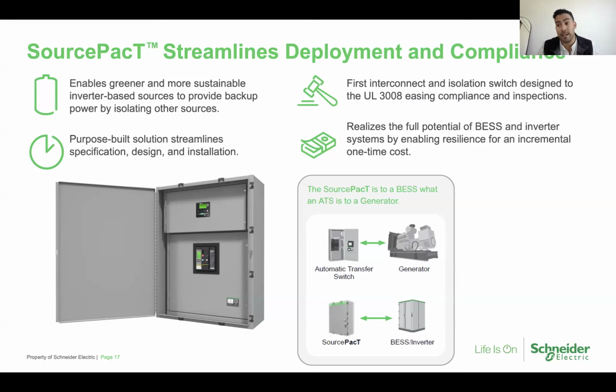These inverters have very smart inverter characteristics. They can operate in a grid interactive, grid tied mode, but also become their own anchor resource, creating their own voltage and frequency to provide backup power. This product helps streamline microgrid deployment, where you have a purpose-built product that's designed specifically for isolation with the controller to sense voltage and frequency outage. As we described earlier, the UL 3008 listing is the first of its kind for an automatic interconnection switch, and it's designed with the testing criteria to be robust and ensure reliability in these systems, much like a transfer switch.